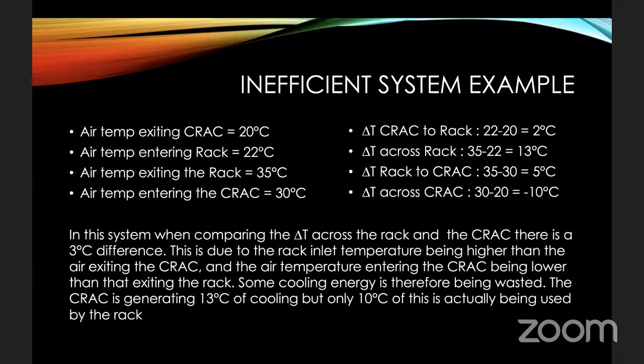So you can see now we have a difference between the delta T across the rack and the delta T across the crack. So this is not an efficient system anymore. We have 13 degrees of cooling. We have 10 degrees of cooling across the crack, but we have a 13-degree increase in temperature across the rack, which means that 100% of the cooling energy is not reaching that rack. If we could improve this system, then we could lower the energy consumption because we wouldn't need as much cooling. Obviously, the servers are still operating at a reasonable temperature because the exit temperature is 35 degrees. So our servers are not overheating, but maybe those servers could do more work if I could get 20-degree air to them instead of 22-degree air.